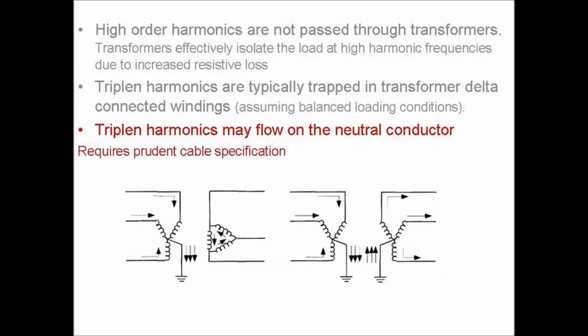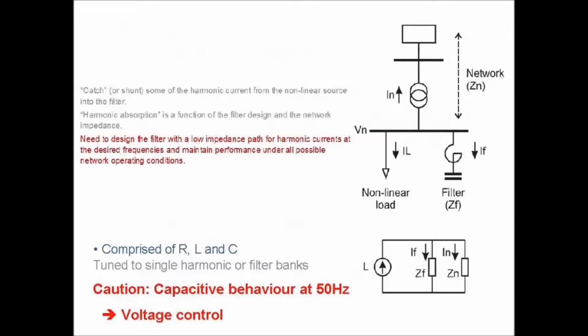The other one I mentioned was transformer winding connections. Basically, if they're Y delta transformers, you can catch some of the triplen harmonics, or the 3rd, 6th, 9th, or whatever, in the actual windings of the transformers themselves. And also, transformers are very good in terms of they're a big tank that absorbs harmonics, particularly at higher frequencies. So the higher frequency harmonics tend to not be able to pass through transformers. So there's an idea for the triplens. They can just circulate forever in your delta windings, but you need to make sure that it doesn't overheat or whatever. And then the other thing to remember is that triplen harmonics can flow on a neutral conductor, so you need to make sure that neutral cable is fairly highly spec'd, or you could have overheating, and that's not good for a transformer.